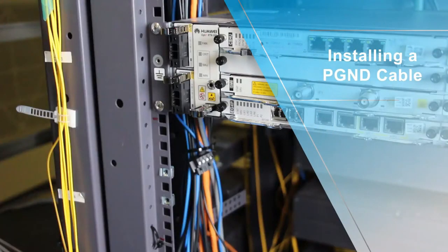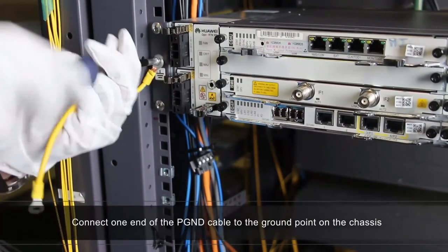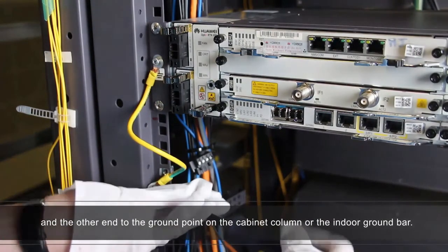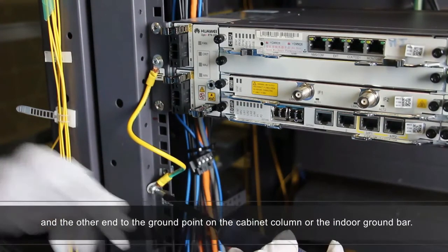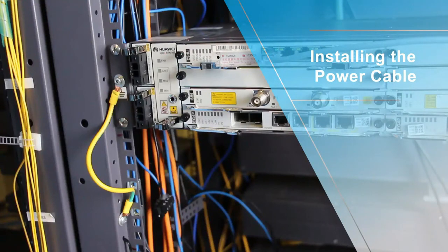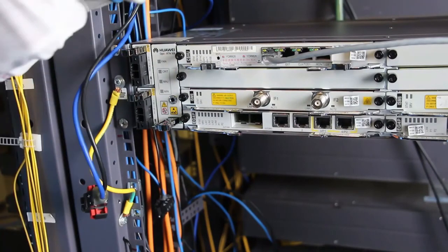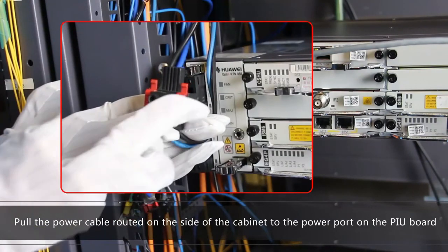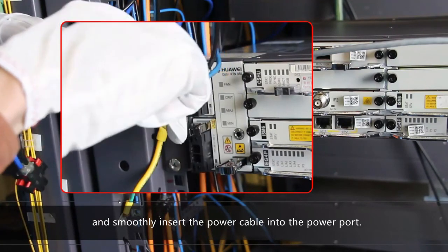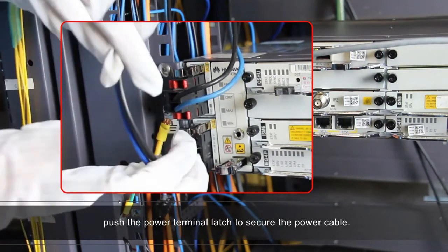Installing a PGND cable: connect one end of the PGND cable to the ground point on the chassis and the other end to the ground point on the cabinet column or the indoor ground bar. Installing the power cable: route the power cable along the side of the cabinet to the power port on the PIU board and smoothly insert it into the power port. After the power cable is completely inserted, push the power terminal latch to secure the power cable.